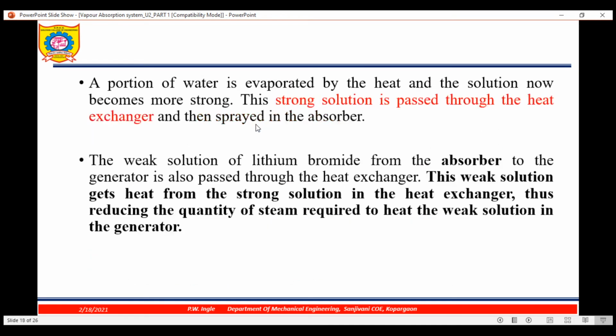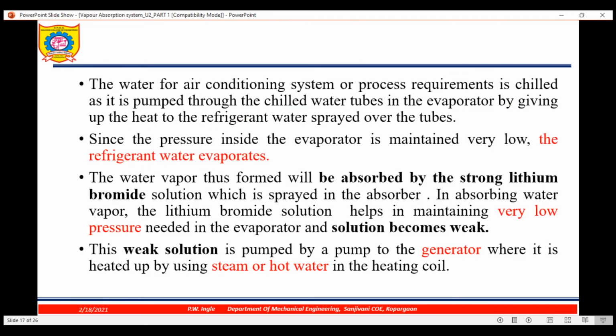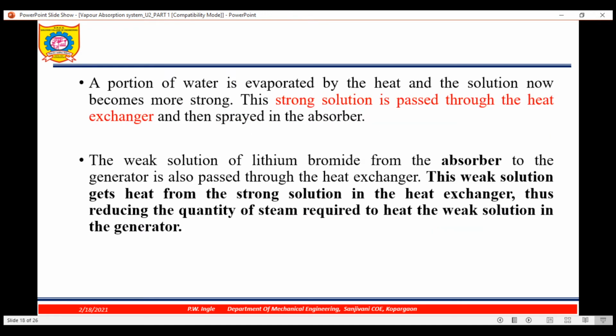Now next, the portion of water is evaporated by the heat and the solution now becomes stronger. Now what is happening in the generator? This water which was absorbed by the lithium bromide solution will get separated out because of steam or heating coil. Okay. And then we are getting what? Strong solution. This strong solution is passed through the heat exchanger and then sprayed in the absorber.